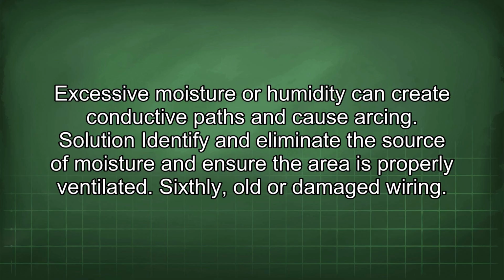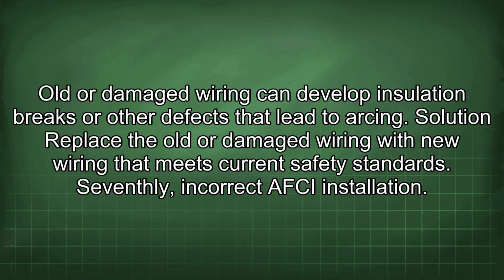Fifthly, moisture or humidity. Excessive moisture or humidity can create conductive paths and cause arcing. Solution: identify and eliminate the source of moisture and ensure the area is properly ventilated. Sixthly, old or damaged wiring. Old or damaged wiring can develop insulation breaks or other defects that lead to arcing. Solution: replace the old or damaged wiring with new wiring that meets current safety standards.